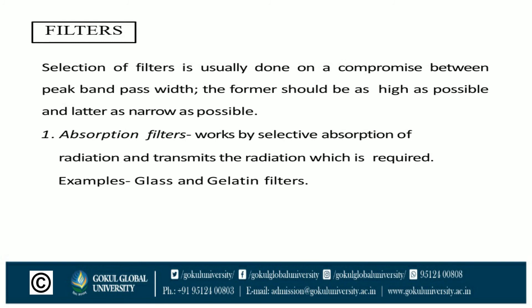Selection of filters is usually done on a compromise between peak transmittance and band pass width. The former should be as high as possible and the latter as narrow as possible. Absorption filters work by selective absorption of radiation and transmit only the required radiation. Examples include glass and gelatin filters.